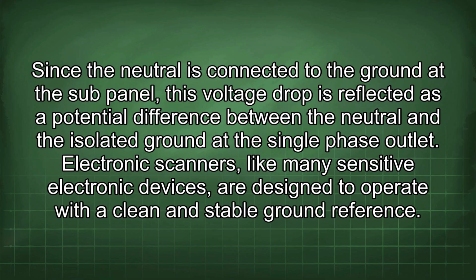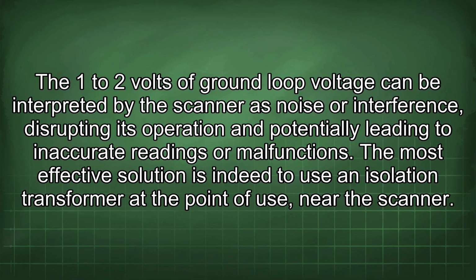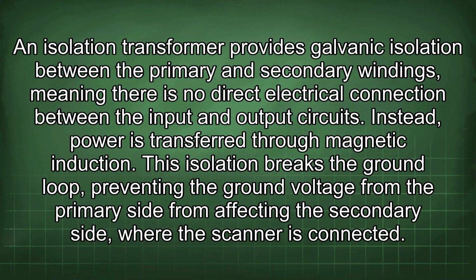Electronic scanners, like many sensitive electronic devices, are designed to operate with a clean and stable ground reference. The 1 to 2 volts of ground loop voltage can be interpreted by the scanner as noise or interference, disrupting its operation and potentially leading to inaccurate readings or malfunctions. The most effective solution is indeed to use an isolation transformer at the point of use near the scanner. An isolation transformer provides galvanic isolation between the primary and secondary windings, meaning there is no direct electrical connection between the input and output circuits. Instead, power is transferred through magnetic induction.